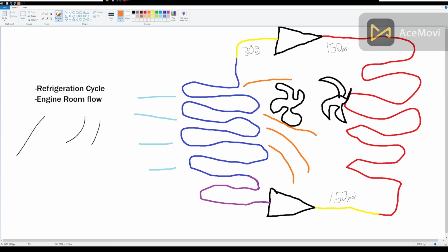So while we are going to say that you have very cold liquid in this part of the line, it's actually going to be about a 90% liquid, 10% gas mixture, but that's going to complicate it for the scope of this video. I've probably already messed you up enough by not swapping my scene over to paint. We're not going to worry about how much flash gas there is. And in an engine room, your flash gas is largely taken care of by your vessels anyway. And we're going to get there in a moment.